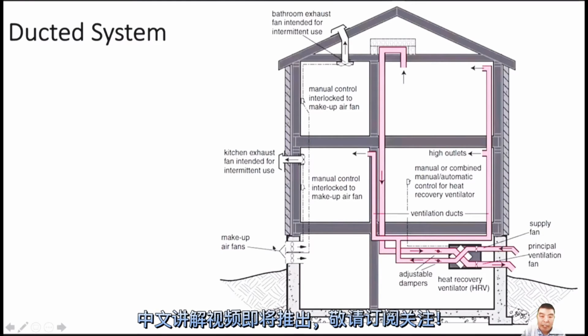Yeah, so they have the make up air fans, and if you don't have this one, sometimes we can use the HRV for the make up air. Yeah, so we just balance the intake and outlet pressure. Make sure all the outlet CFM is almost the same as the inlet. That keeps the pressure better, and you will feel better.